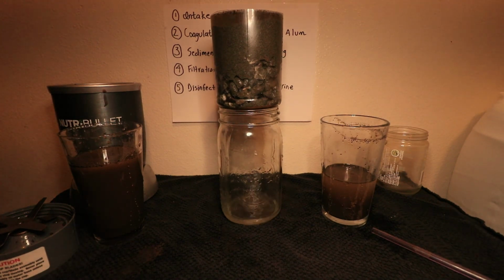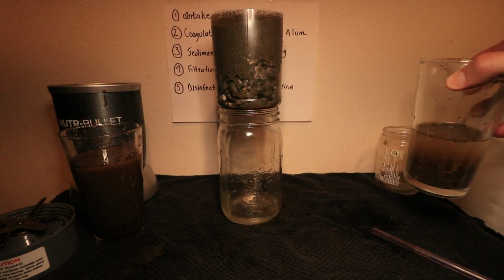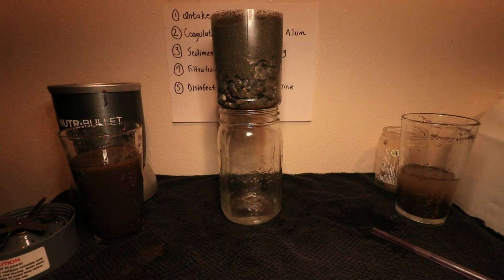And then finally, the last step of the drinking water treatment process is disinfection. And there's a couple different prominent ways of going about disinfection. One is adding chlorine, and chlorine has a benefit of killing bacteria, virus, and protozoan cysts right there. And then it has a residual that lasts through the distribution facility, so through the pipes there's still some chlorine in there, and it may be able to kill those pathogens that are lingering around or introduced later on.